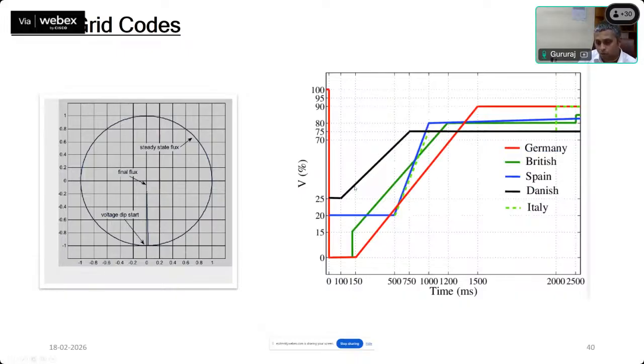What this suggests is you're supposed to stay connected to the system even if it is zero voltage right through. That means even if it is a bolted short circuit fault at the grid side for some duration. See the amount of struggle that DFIG has to pass through during this time, right? And then there is the Spain grid code, British grid codes, Danish, Italian, Indian. India also has its own grid codes. Depending upon the severity of the grid code demands, they will not be able to disconnect in these regions.